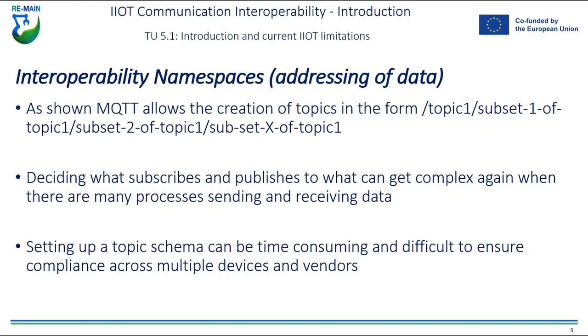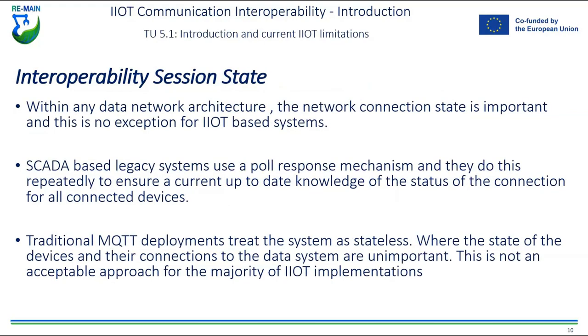The other issue is session state. With any data network architecture, the network connection state is important, and this is no exception for IoT-based systems. SCADA-based systems use a poll-response mechanism, repeated continuously, to ensure current and up-to-date knowledge of the status of the connection for all connected devices. Traditional MQTT deployments treat the system as stateless, where the state of devices and connections is considered unimportant — which is not acceptable for the majority of industrial implementations.